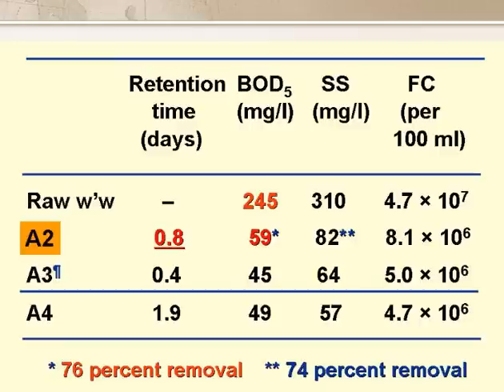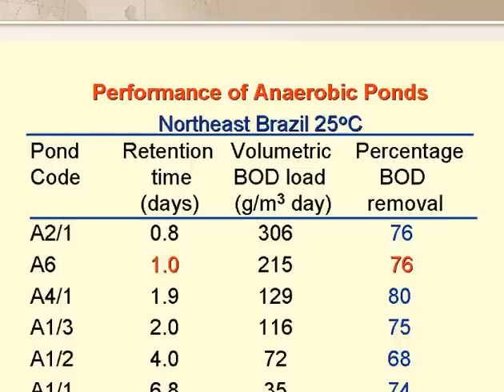These were the results. Pond A2, which had a retention time of 0.8 day, reduced the BOD from 245 mg/L to 59 mg/L — that's a removal of nearly 76%. The other ponds didn't perform as well, and the whole set of results from these and other anaerobic ponds at the same site showed that the percentage BOD removals are much of a muchness, and really for this strength wastewater, there's no point in having a retention time longer than one day.